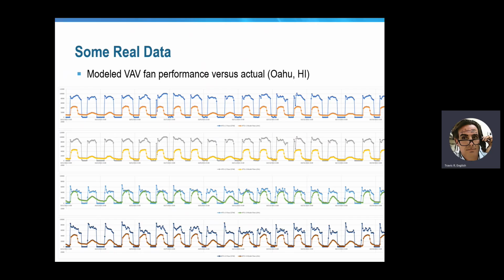In this case, we did have CFM points on all the air handlers, and we were able to extract the airflows out of the energy modelers. So what you're looking at here is airflow in CFM for each of four air handlers. The lower line is showing the modeled CFM, and then the top line is showing the actual CFM. And I want to point out a couple things.